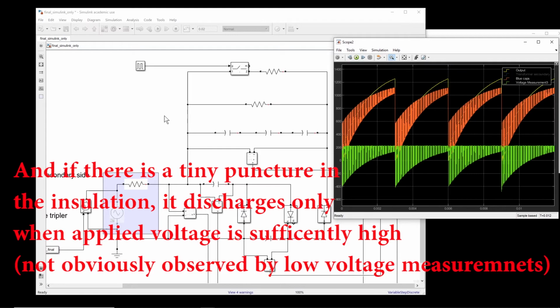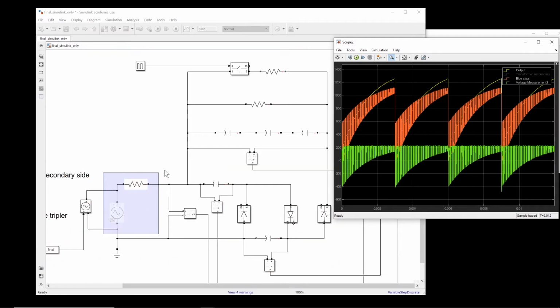But when high voltage stress is applied over them, because of this conductive path that is formed within the capacitors, they become field dependent -- when the electric field is high, more current can pass through them. It's not linear. And therefore, only when you put them inside a high voltage circuit do they fail to perform properly. But when you measure them with a multimeter, they more or less behave as a normal capacitor.